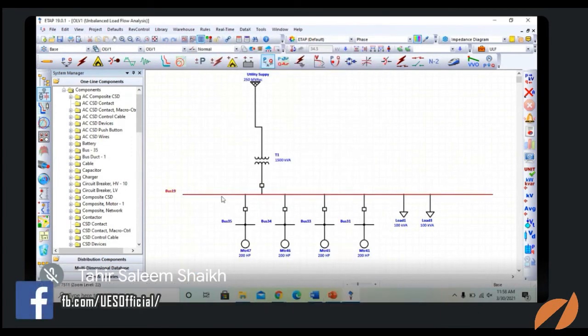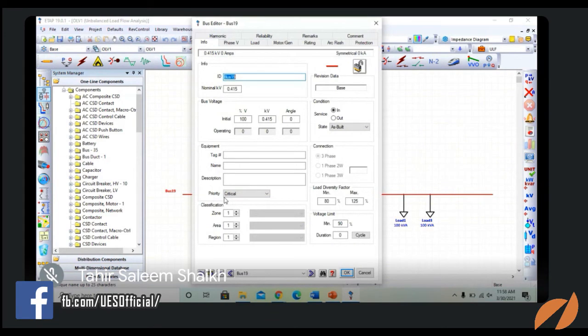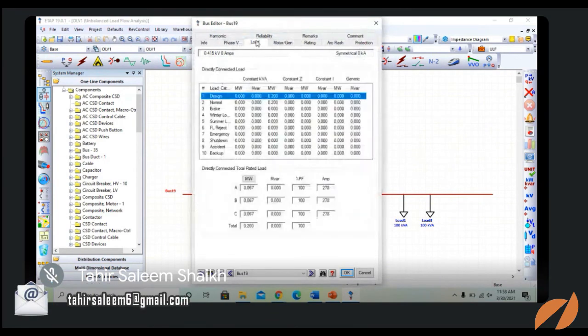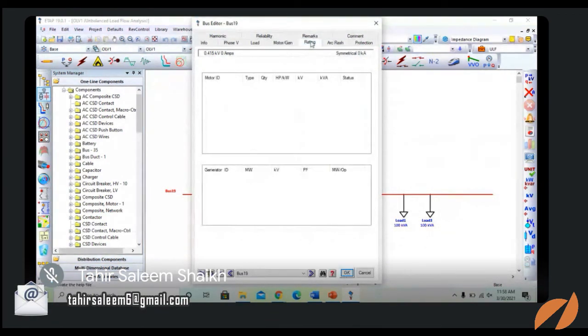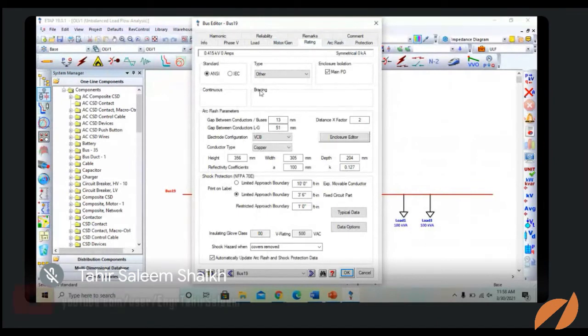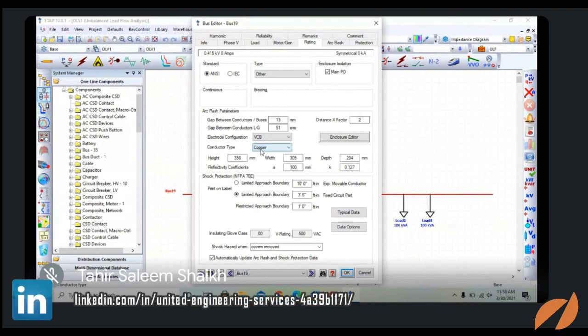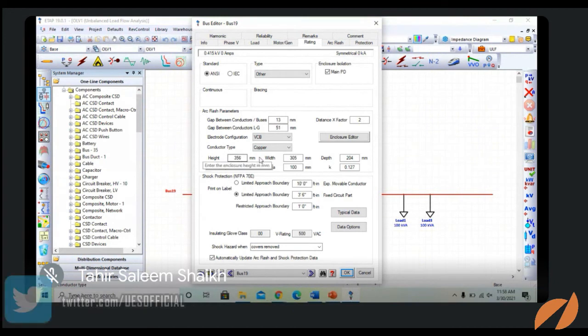Okay, now for the bus setting, these are the different settings which you have to put. Here you can select the material of the conductor type, aluminum or copper. As I've already told you, there are two types which you will find in ETAP. What is the height and width of the shock protection? That is according to NFPA 70E.